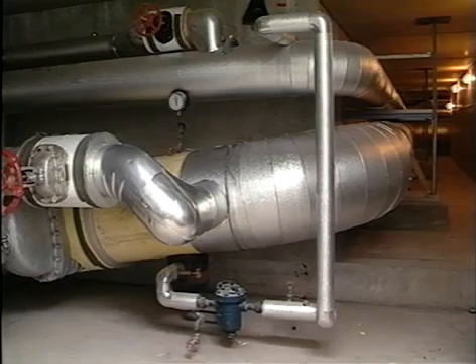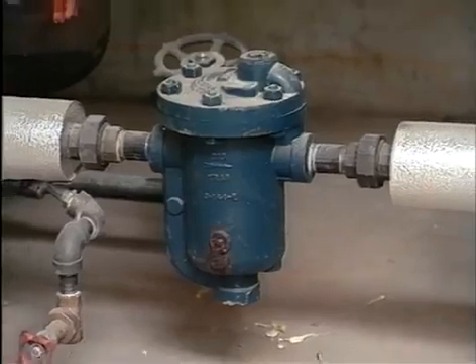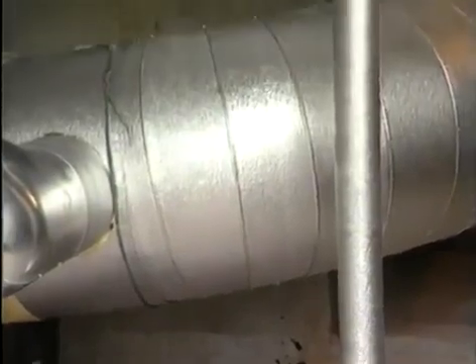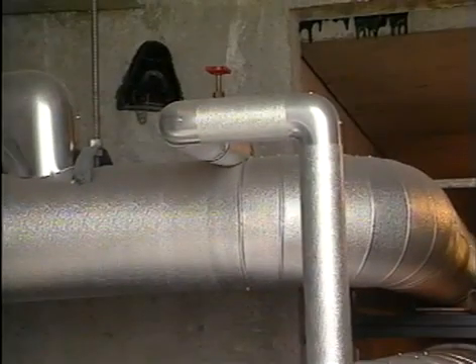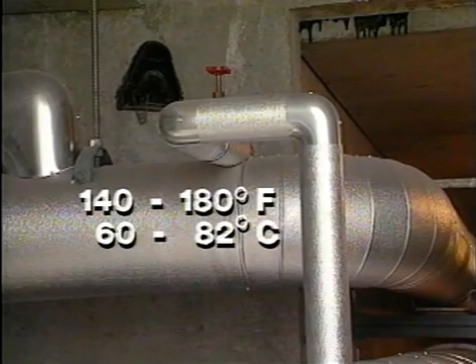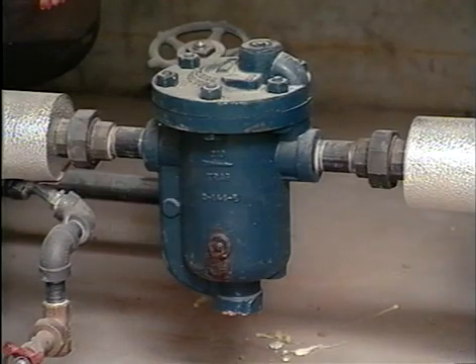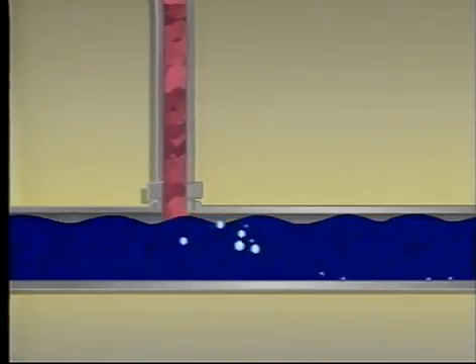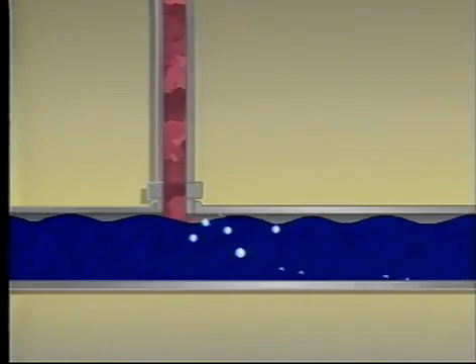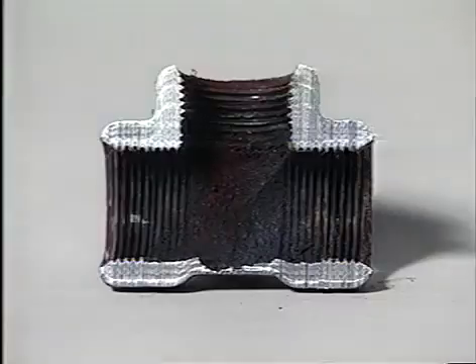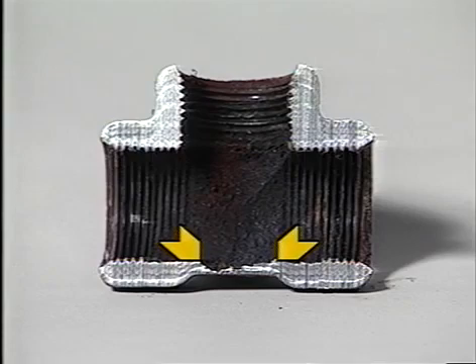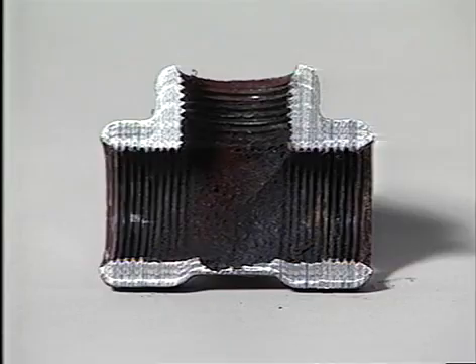One likely place for thermal shock to occur is in steam utility corridors. In these areas, the drip traps from high-pressure steam mains often discharge directly into the pumped condensate return lines. The temperature of the condensate in these lines usually ranges from 140 to 180 degrees Fahrenheit. The condensate being discharged from the steam trap is at nearly steam temperature when it passes through the trap orifice. When the trap discharge enters the low-pressure condensate line, a great deal of it flashes back into steam. The flash steam immediately collapses again when it encounters the relatively cool pump discharge water. This thermal shock often causes damaging water hammer. The localized sudden reduction in pressure near the wall chips away piping and tube interiors. Oxide layers that otherwise would resist further corrosion are removed, resulting in accelerated deterioration of piping and equipment.